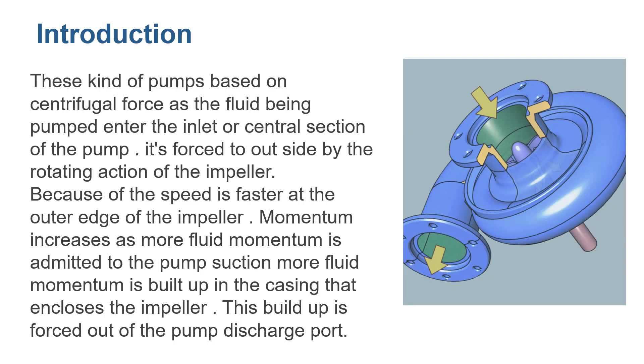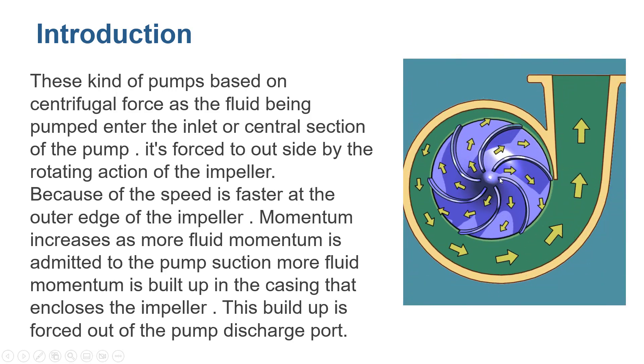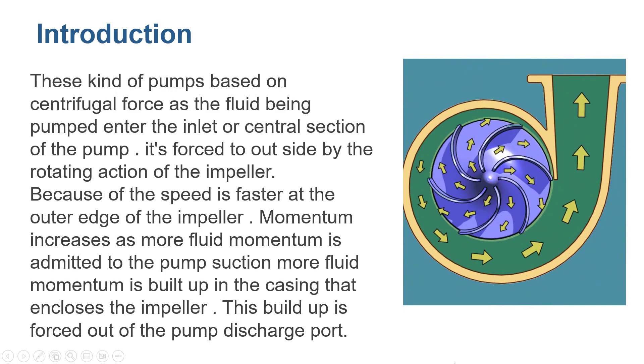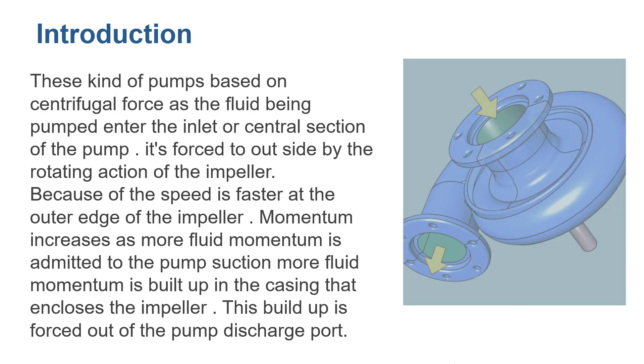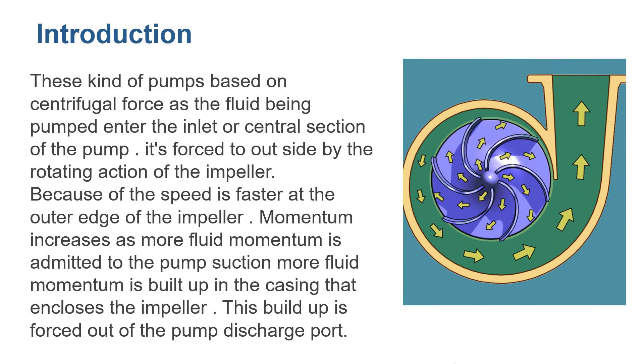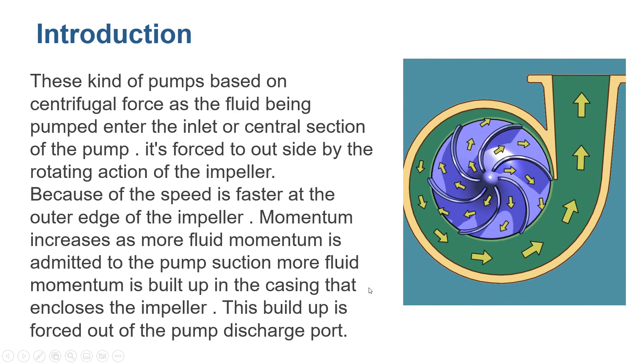First we start with the introduction. This kind of pump is based on centrifugal force as the fluid being pumped enters the inlet or central section of the pump. This is the central portion where the impeller is rotating. The water enters the center portion of the impeller. Because the speed is faster at the outer edge of the impeller, momentum increases as more fluid is admitted to the pump suction. More fluid movement is built up in the casing that encloses the impeller, and the buildup is forced out through the discharge port.